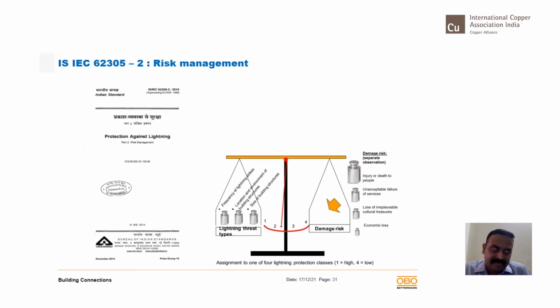Now, how do we design it? The standard insists on a detailed risk assessment for a lightning protection system, which has several factors, as I told you at the beginning, like the number of thunderstorms per square kilometer per year, the location of the building, what type of building it is, what the dimensions of the building are, how many people will be involved inside and for how many hours, whether the building has a surge protection device or not, whether it has a fire alarm which is automatic or manual, whether the cable entering the building is an overhead line or an underground line. So all these kinds of inputs are to be provided. With that, you will have to evaluate the damage. So you will have to strike a balance between the lightning threat available and the damage risk that can possibly happen. So what are the threats?